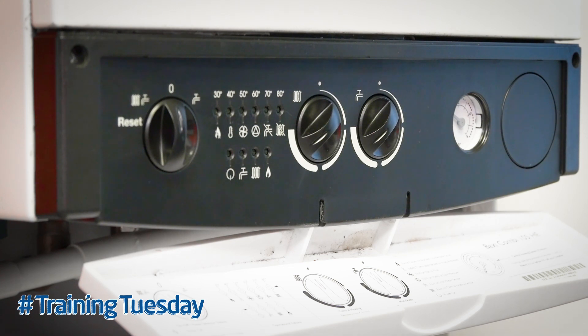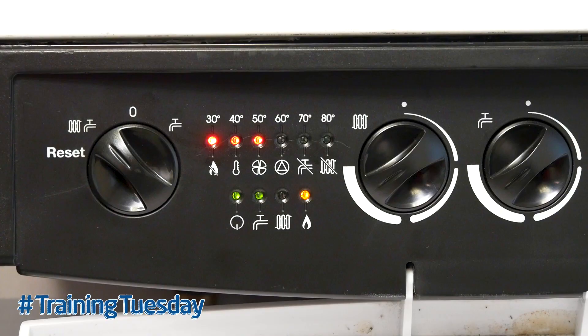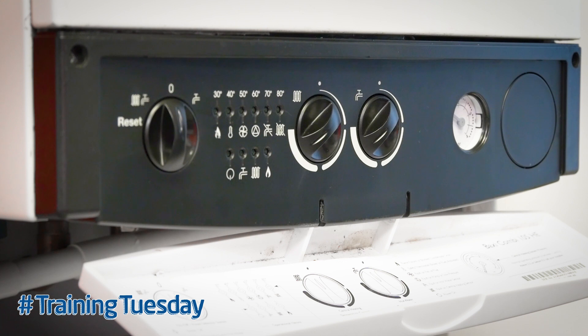If on the other hand the lights on the front of the boiler increase very quickly, then you've confirmed that the primary system water can't get through the plate heat exchanger quick enough and the boiler is shutting down on temperature. Therefore the plate heat exchanger is either blocked or restricted — change the plate heat exchanger and away you go.